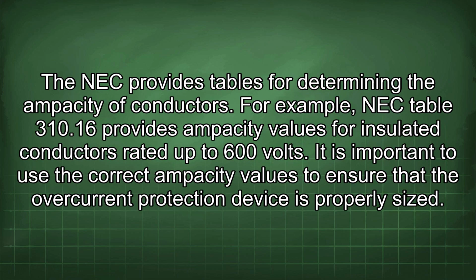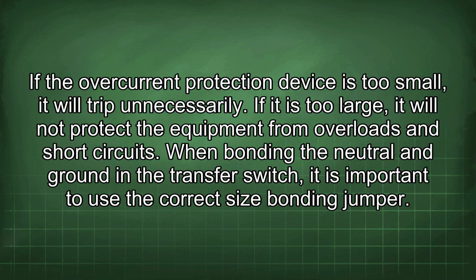Their ampacity is determined by their size and insulation type. The NEC provides tables for determining the ampacity of conductors. For example, NEC Table 310.16 provides ampacity values for insulated conductors rated up to 600 volts. It is important to use the correct ampacity values to ensure that the overcurrent protection device is properly sized. If the overcurrent protection device is too small, it will trip unnecessarily. If it is too large, it will not protect the equipment from overloads and short circuits.